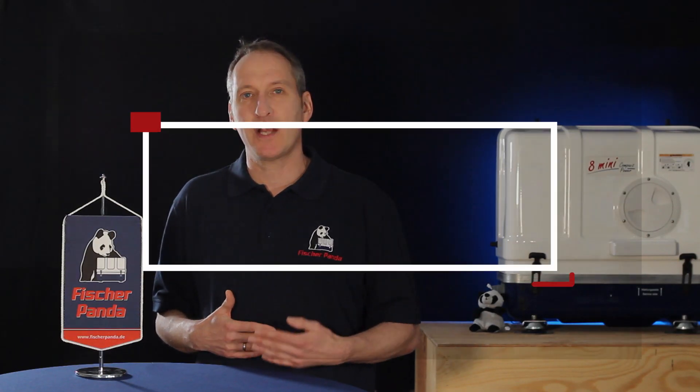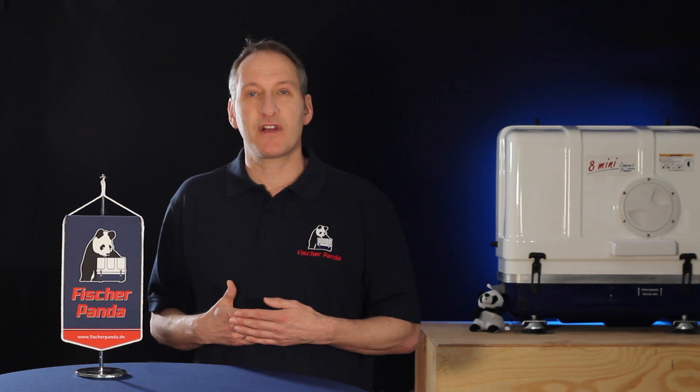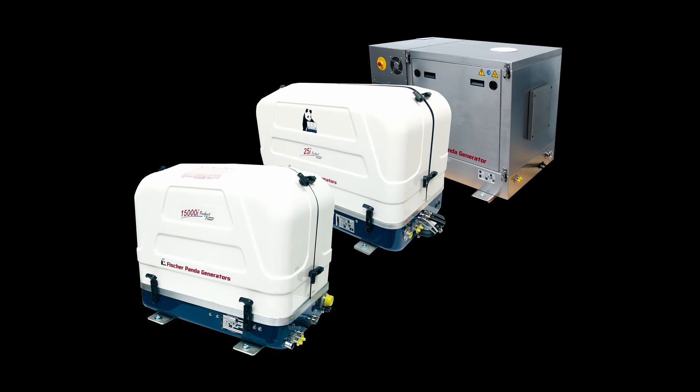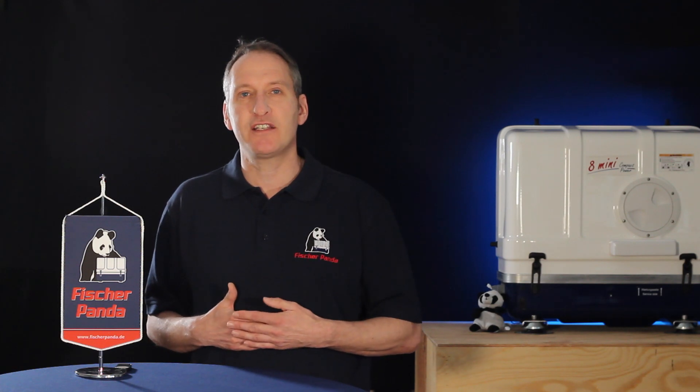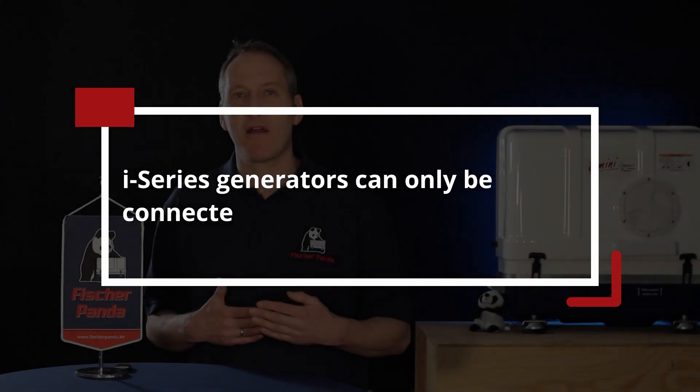The second type of Fischer Panda generators that can be connected in parallel are the I-Series generators. These are variable speed generators using inverter technology. With the Fischer Panda I-Series generators it's possible to connect up to three generators together in parallel, allowing much more flexibility for your system planning. Because the output power is provided from the inverter, this allows you to connect different rated generators together in your system — but you do need to use parallel-capable inverters.